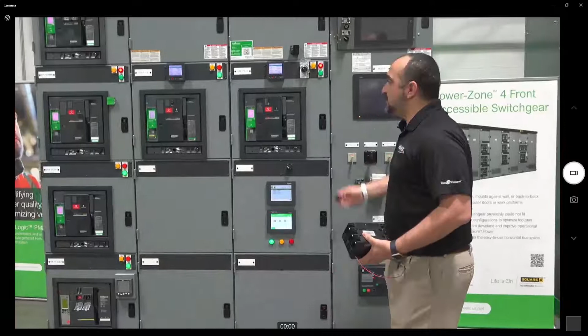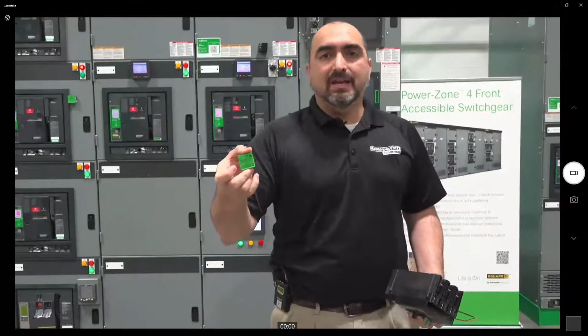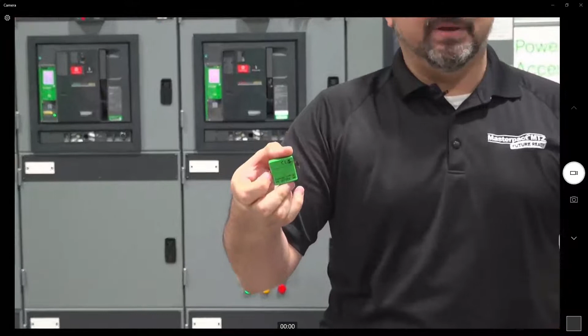A lot of other things that could be communicating inside equipment today are sensors, as small as what I have in my hand, that can tell us how hot joints inside the equipment are. Once we know the current flowing through a joint and how hot it is, we can do interesting analytics - for example, if it's hotter than normal but the load hasn't increased, could that indicate a loose joint somewhere? You can do a lot of interesting things by leveraging connected architectures.